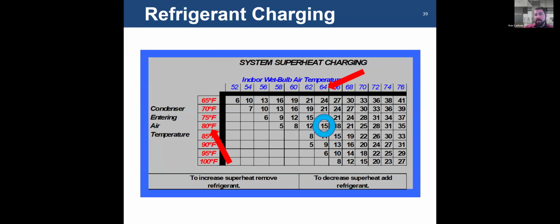This is a typical chart of what the manufacturer may provide for you. It gives you an indoor wet bulb temperature. It gives you the wet bulb temperature because the capacity of your coil is a combination of latent load and sensible load. The wet bulb takes this into account.